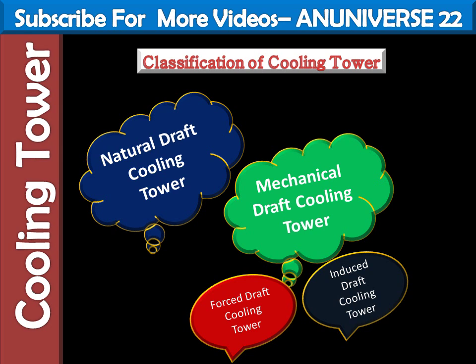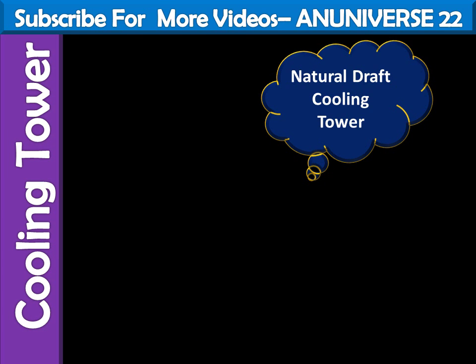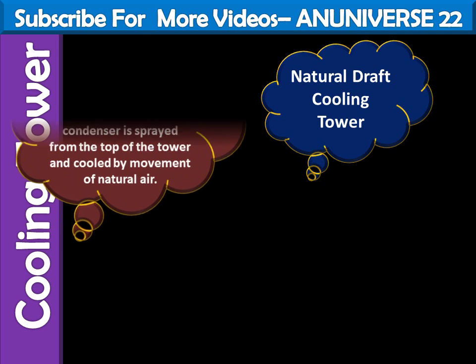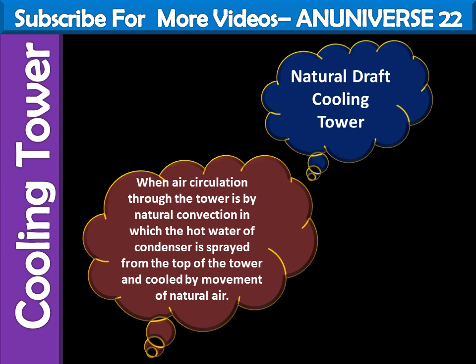Now we will discuss the natural draft cooling tower. Since the air circulating through the natural draft cooling tower is atmospheric air, these cooling towers are also known as atmospheric natural draft cooling towers, or simply atmospheric cooling towers. When air circulation through the tower is by natural convection, in which the hot water from the condenser is sprayed from the top of the tower and cooled by the movement of natural air, it is called a natural draft cooling tower.